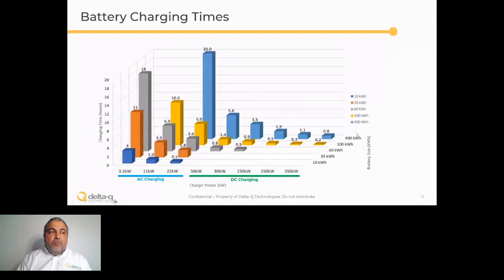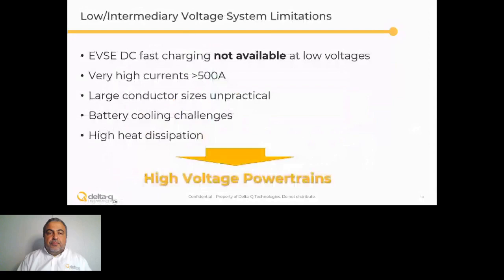The sizes can go up to 400 kilowatt hours. At these sizes, AC charging enables overnight charging, but is not able to support opportunity charging. Therefore, there is a need for shifting to DC fast charging for rates up to 350 kilowatts. So the low and intermediate voltages below 120 volts have some limitations when it comes to actually large machines. The EVSE, the charging station: DC fast charging is not available and not supported at low voltage levels.